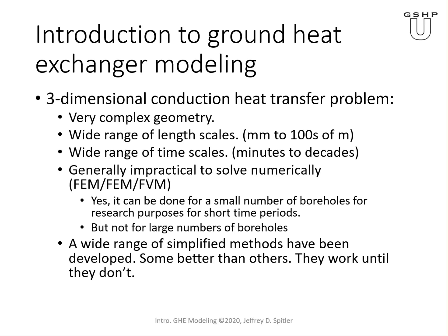We've got a wide range of length scales, so when we're modeling the heat transfer inside the borehole, we might be interested in heat transfer over millimeters. The pipe wall thickness is usually a few millimeters. But in larger ground heat exchangers, or even in single ground heat exchangers, which may be, say, 100 meters deep or deeper, but in large ones, we might have a field that's several hundred meters in each direction. And so we've got a wide range of length scales to resolve.